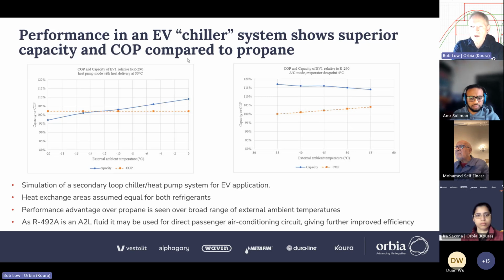In AC mode, the differences are starker. If you look on the right-hand graph, that's AC mode where the evaporator is fixed at around about 2C, just above freezing point. Blue is capacity, so the blend here has got a higher capacity than propane, 15% higher in fact. And the COP is, again, about the same, to rising to slightly better. But with the thought that now with higher capacity, you can have your compressor running quieter. One of the quirks of the car AC world is that the engineers have to think as much about noise and vibration into the cabin as they have to about performance, because people notice compressors rattling and whining away. And so being able to turn the compressor down is actually a big benefit.